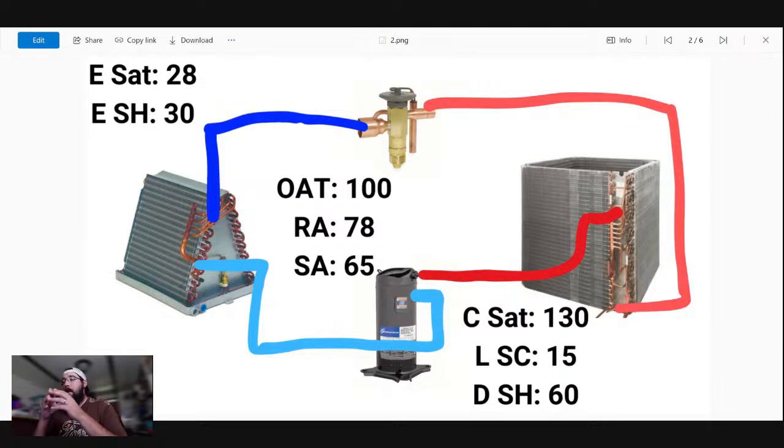Let's see. I do see oil logged. So the evap being oil logged, for example. A oil logged evap, I'm pretty sure that's what you're referring to. That would almost look like more of a low airflow condition. I wouldn't expect that here.